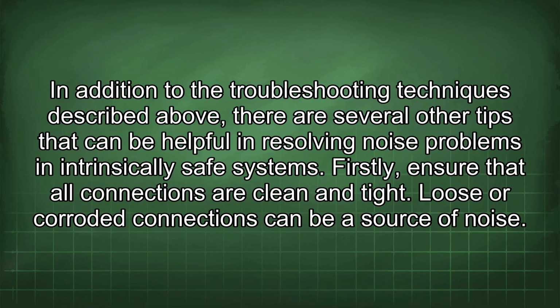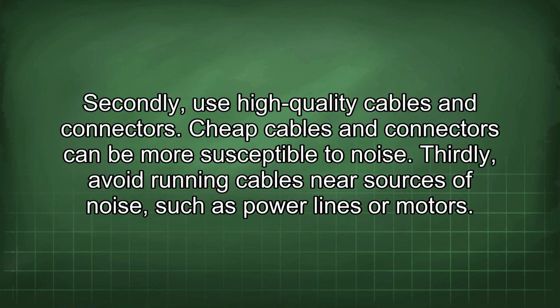In addition to the troubleshooting techniques described above, there are several other tips that can be helpful in resolving noise problems in intrinsically safe systems. Firstly, ensure that all connections are clean and tight. Loose or corroded connections can be a source of noise. Secondly, use high-quality cables and connectors. Cheap cables and connectors can be more susceptible to noise.